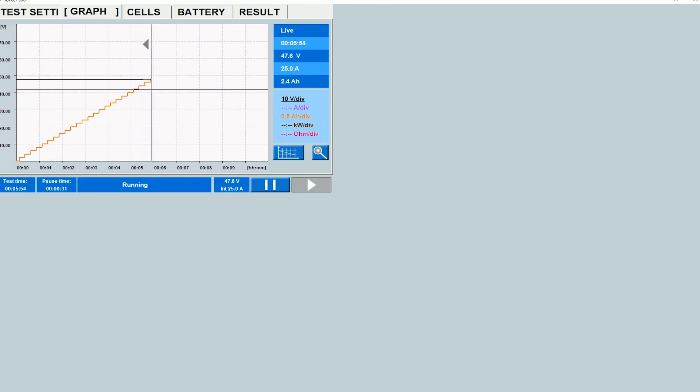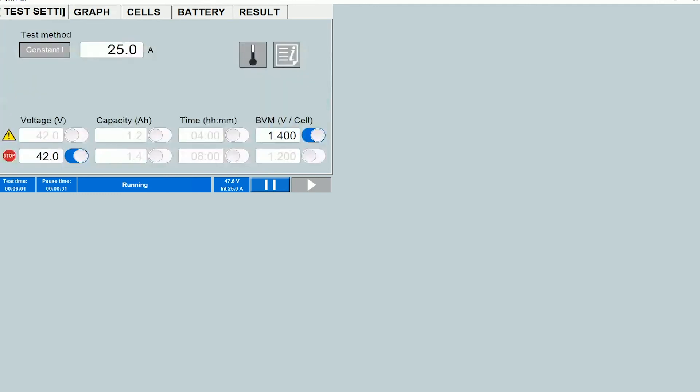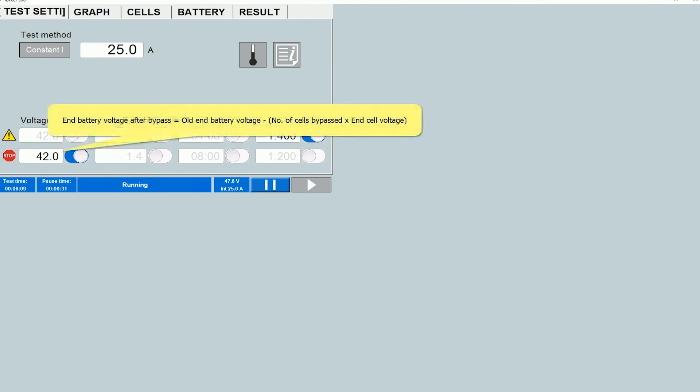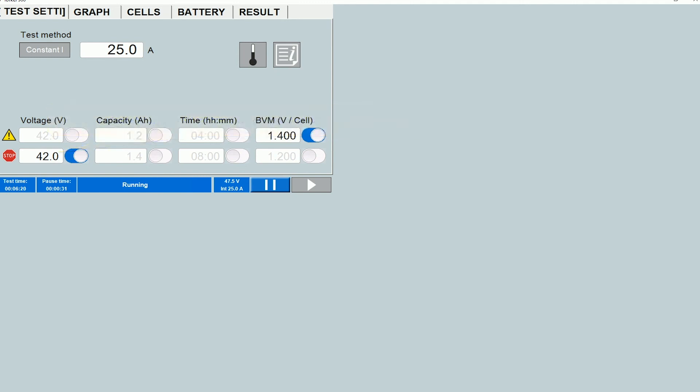If you do bypass some bad cells, what you want to do is go over to the Settings tab and change the end voltage accordingly. So the end voltage would be recalculated by subtracting the end voltage for the number of cells that you have bypassed. So let's say the end voltage is 1.75 volts per cell, and you bypassed two cells. So you would change the end voltage to 1.75 times 2, which would be 3.5 volts. So you would subtract 3.5 from 42 volts and set the new number as the new stop limit for the test.